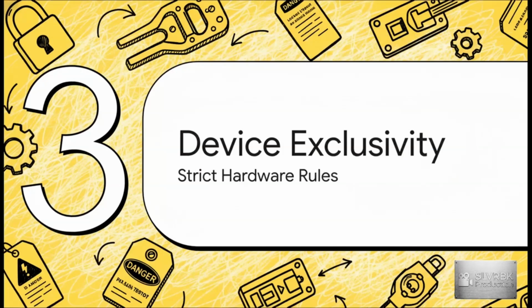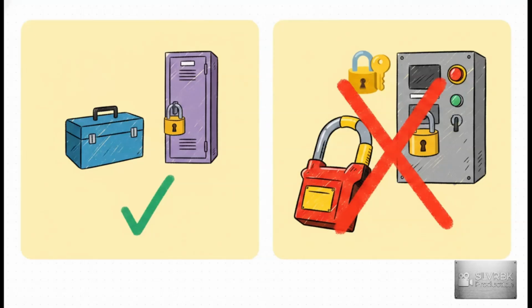Okay, shifting from the administrative side to the physical tools, let's look at Section 3, Device Exclusivity Rules. Whether you're using a lockout or a tagout device, OSHA has a zero-tolerance policy for hardware mix-ups. The padlock you use for your gym locker or to lock up your toolbox, you can never use that on an industrial circuit breaker. LOTO devices have to be singularly identified and used exclusively for controlling hazardous energy, period. You can't use a LOTO lock to secure a fence gate, and you can't use a standard master lock on a heavy machine. They have to be the only devices authorized for this purpose in your building.